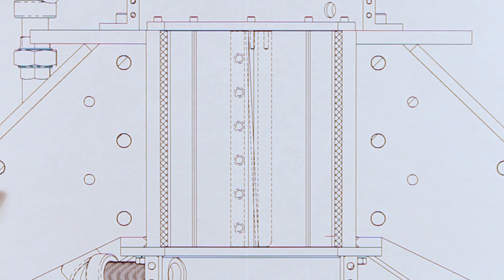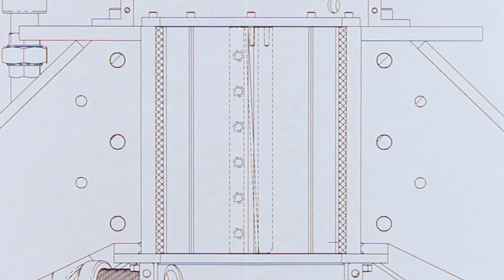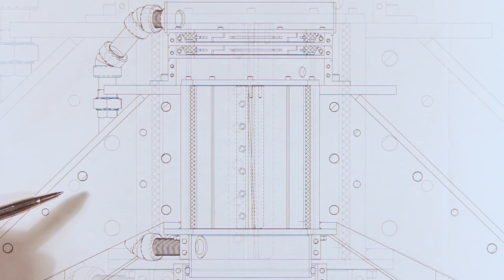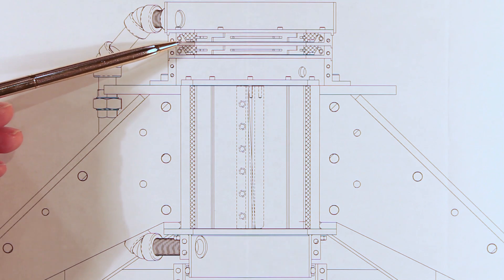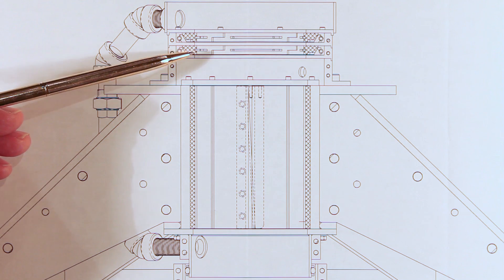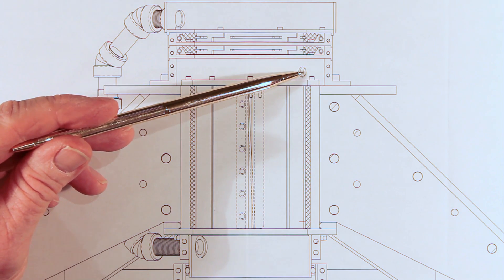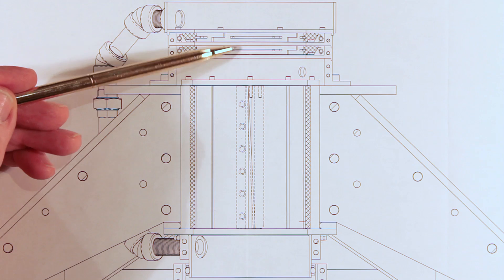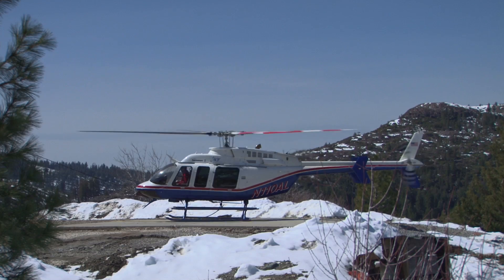The water lubricated bearing is made in two replaceable halves. A split and tapered bronze key set is used to lock the bearing in place and permits quick and easy inspection or replacement with no major disassembly. The water lubricated conversion design uses filtered water to lubricate both bearing and seal. We see a two-row segmented polymer seal positioned above the bearing, with two ports below the seal for injection of pressurized filtered water. This water flows down through the bearing and also up through the seal. With everything measured and inspected, the bearing and seal package is crated and made ready for its trip to the mountains.